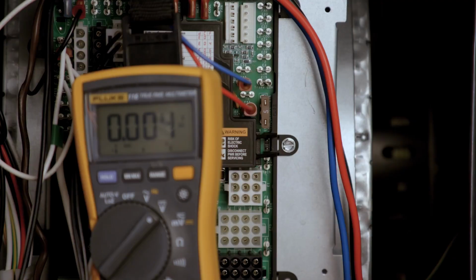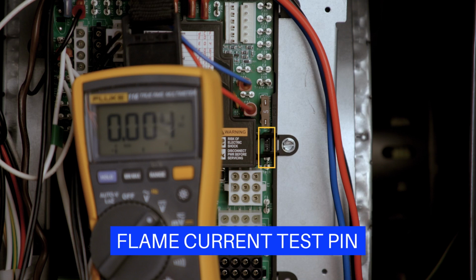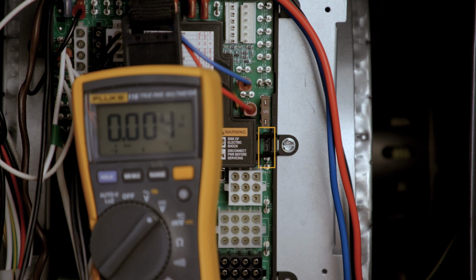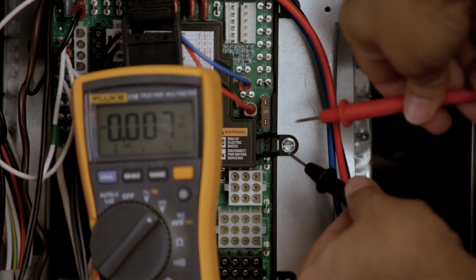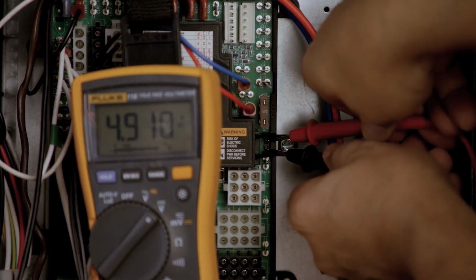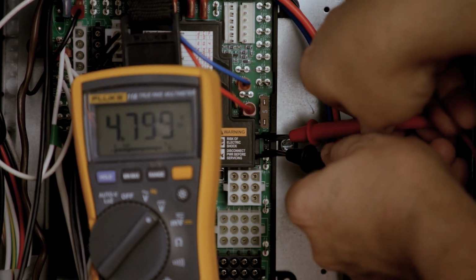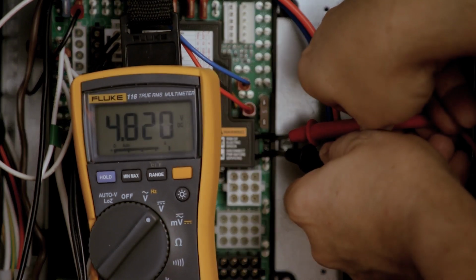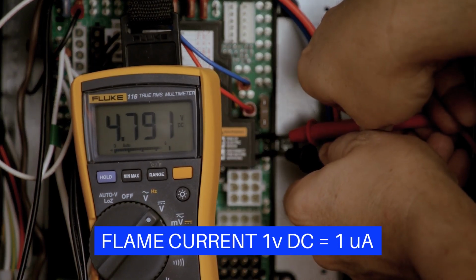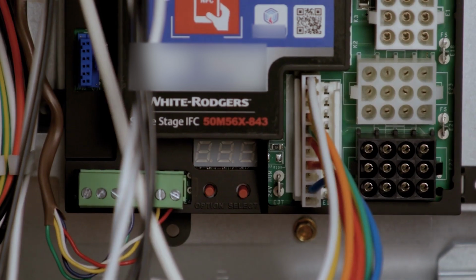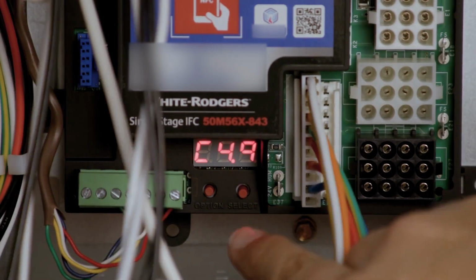The 50M56X-843 comes with flame current test pins. These pins are easy to access and provide the flame current reading. To test the flame current, set a voltmeter to DC volts and measure across the pins while a flame is present on the sensor probe. 1 volt DC equals 1 microamp. With the 50M56X-843 control flame current display feature, the current can now be easily checked on the digital display without a meter.